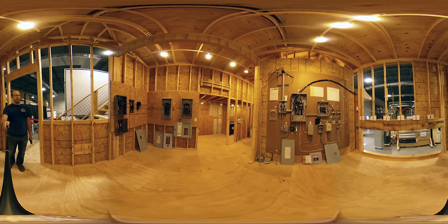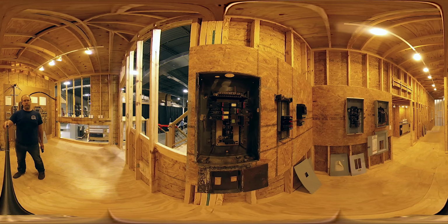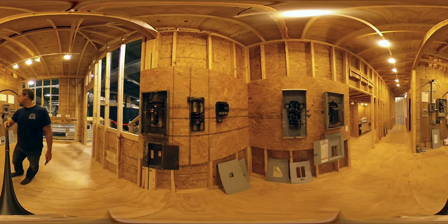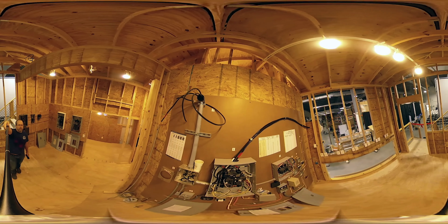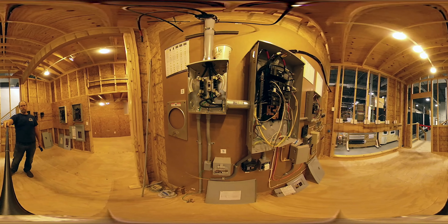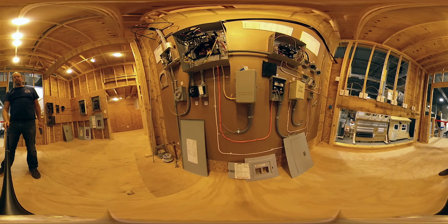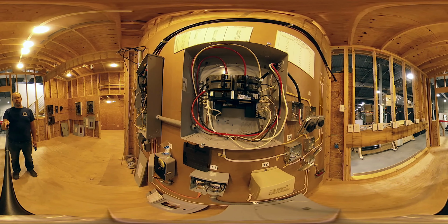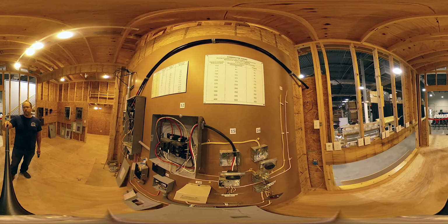And in the electrical room, behind you, if you turn, we have some old electric panels like Federal Pacific, Zinsco, fuses. So you can see real electrical panels that have been pulled out of a house that have defects. And this wall here takes you through from telephone pole and mast down to the meter and all the components that you would come across during an inspection. Main distribution panel, shut-off switches, devices, receptacles, outlets, timers, fuse disconnects, sub-panel, and dryer or stove outlets, 3-prong, 2-prong, 4-prong, and wall receptacles, switches. Some of them are properly installed, some are incorrectly installed.